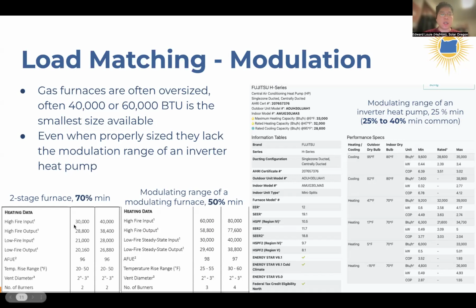But with a two-stage furnace, if it's 40,000 BTUs, the first stage, the low stage, is still 28,000 BTUs. So if your home needs 10,000 BTUs on a mildly cold day, then the two-stage furnace, even on the low output, is oversized by quite a bit. And so you don't get the runtime needed to keep those exterior surfaces continuously warmed at a low rate of output. Same thing with modulating furnaces. A 60,000 BTU modulating furnace might only be able to modulate down to 30,000 BTUs, which is still a lot of output for a home on a mild day. So the conclusion from this slide is that modulating heat pumps or inverter driven heat pumps have a much larger modulation range than the best multi-stage or modulating gas furnaces.